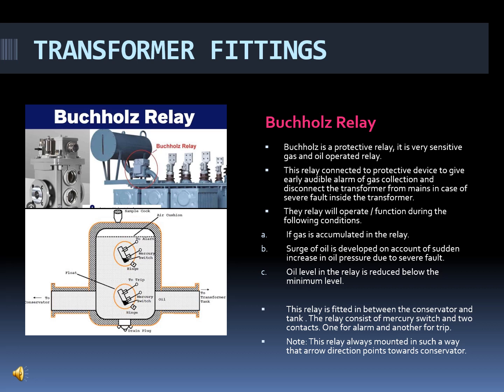This relay is fitted in between the conservator tank and the main tank. I have enclosed the image, you just look into the image. This relay consists of two mercury switches, and each mercury switch serves one for alarm and the other for trip indication. The relay is always mounted in such a direction that the arrow direction should be towards the conservator tank. Just see, I have enclosed the Buchholz relay, which is a very important relay in transformer protection.